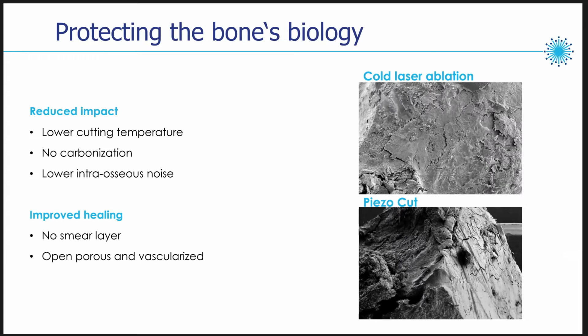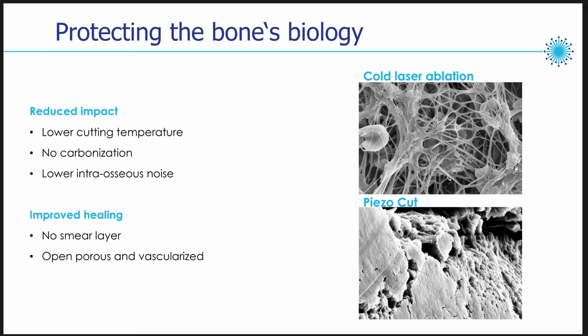Here you see a scanning electron microscopy image of the cut surface in a comparison between our laser at the top and a traditional piezo instrument, for example. Other mechanical instruments look alike. So you clearly see the difference between the surface that we create and a traditional instrument, which pushes the debris into the tissue. With our laser, we have an open and porous surface that is biologically active immediately after cutting. It starts to bleed immediately and starts to heal immediately. We have preclinical data that demonstrate that healing kicks in faster with our device in comparison to traditional mechanical instruments.